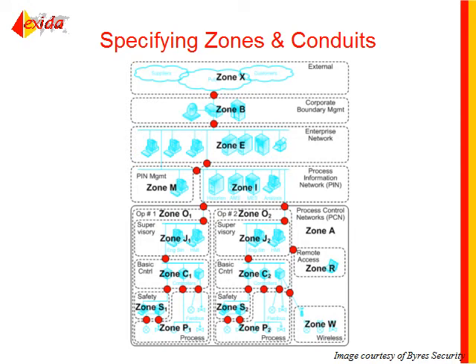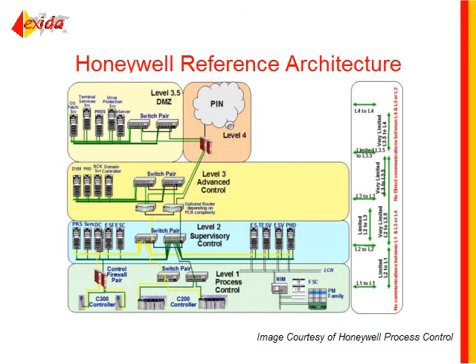There are a lot of different models or reference models for zoning systems, and there's not necessarily a right or wrong answer, but there is best practice. This diagram shows a generic model breaking down from the outside, from the internet, through multiple layers: the corporate management boundary, the enterprise network, then the plant information system. Even within the plant there may be different operating units considered separate zones since they don't share the same security requirements. Within each operating area: a supervisory zone, a control zone, and notably a dedicated zone for safety systems. Also shown are wireless and remote access zones.